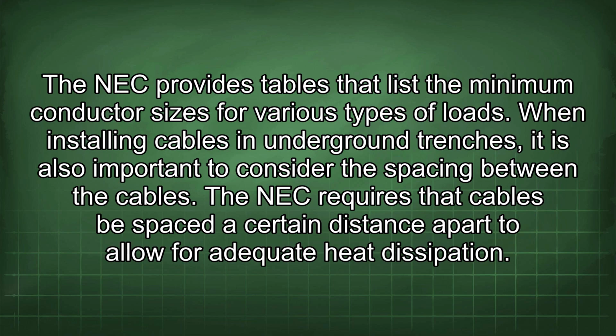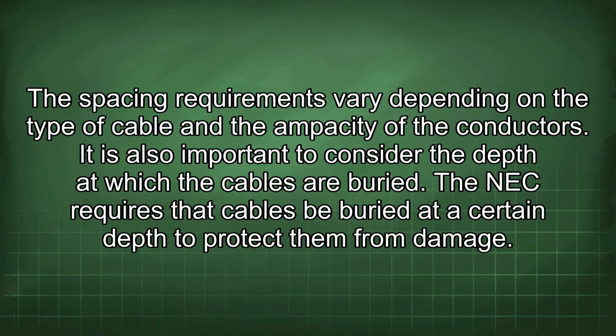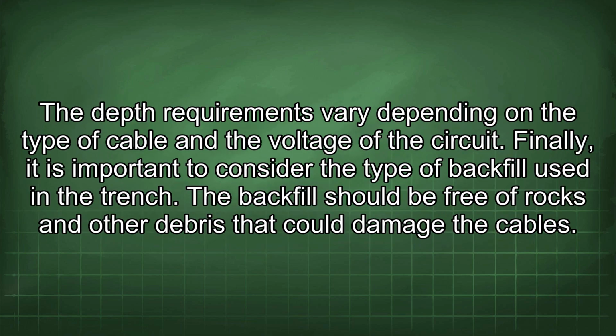When installing cables in underground trenches, it is also important to consider the spacing between the cables. The NEC requires that cables be spaced a certain distance apart to allow for adequate heat dissipation. The spacing requirements vary depending on the type of cable and the ampacity of the conductors. It is also important to consider the depth at which the cables are buried. The NEC requires that cables be buried at a certain depth to protect them from damage. The depth requirements vary depending on the type of cable and the voltage of the circuit.